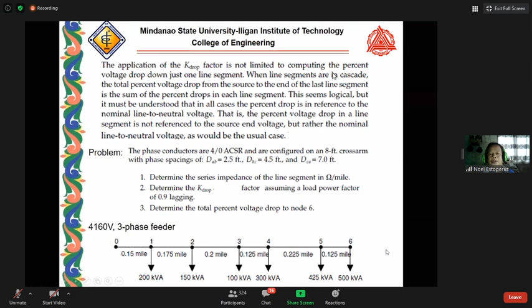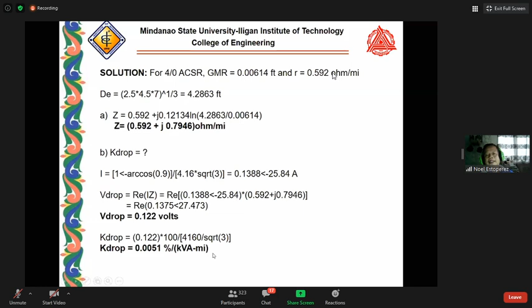So for the solution, we will solve for the Z. The Z here is 0.592 ohms per mile plus j0.7946 ohms per mile. The K drop will be obtained after solving for the voltage drop. So we have here 0.0051, so 0.0051% per kVA per mile. Okay, so this is now the situation, and we find the total percent voltage drop from node 0 to node 6.